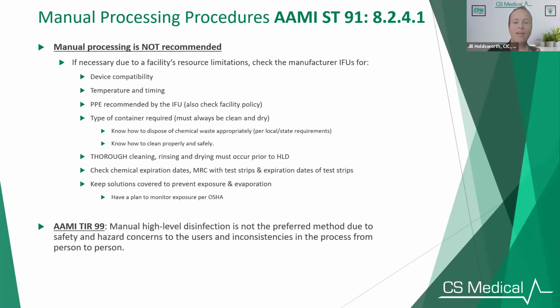Can you time that? And these chemical test strips, I know any of us that have gone through a Joint Commission or DNV survey, we know about these chemical test strips, the expiration dates on these test strip bottles. We know what a pain that is, and that we've probably been cited for it at some point or the other. AAMI TIR99 also says manual high-level disinfection is not the preferred method because it is a safety hazard and there are concerns for users. And there's such an inconsistency in process from person to person. So if you can automate even just the high-level disinfection process, we want you to do that because it is safer for the patients, it's safer for the processing staff, and it takes care of a lot of that human error and inconsistencies in process.